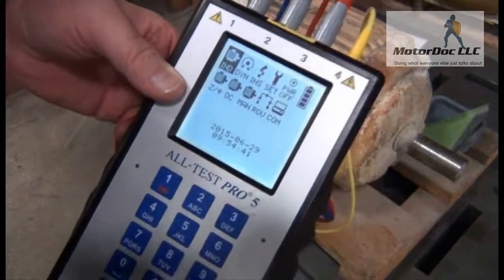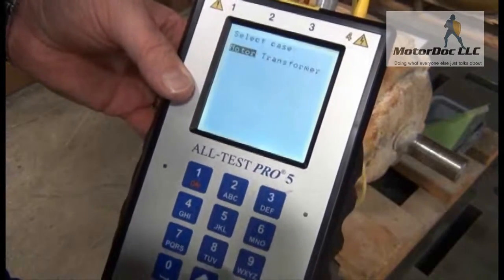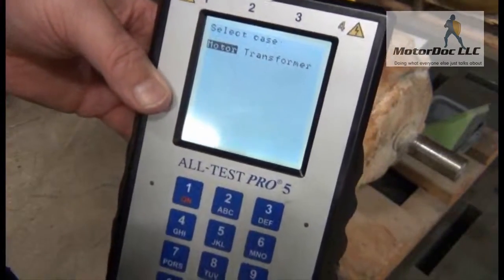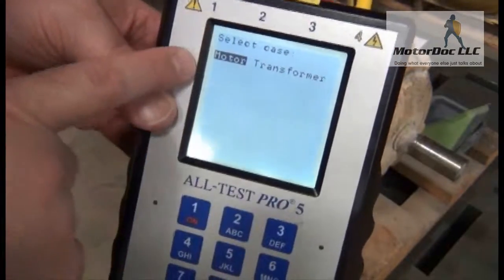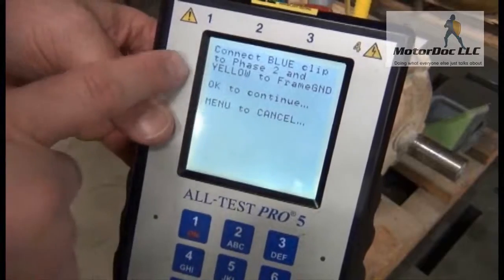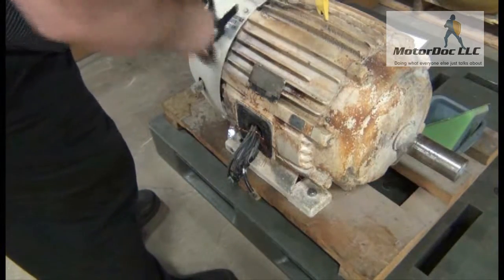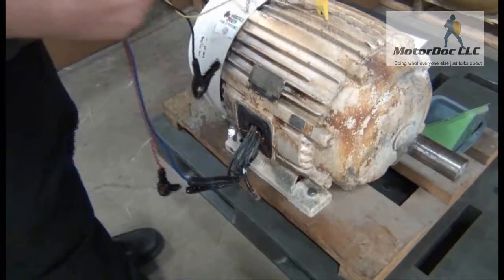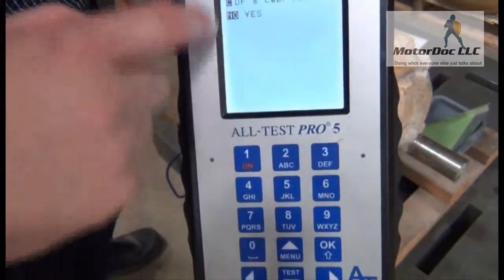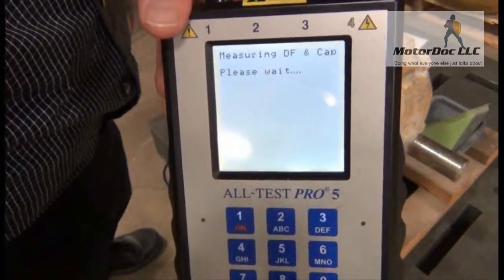Okay. Now we're going to do the demo on the other features, which in this case, I will be doing the motor test. So I select that. And I've got the option of doing a motor or transformer. Cause yes, this will do transformers, DC motors, coils, do comparisons, trending and everything else. So this case, I'm going to do the motor press. OK. Does the same thing as the other measurements, the yellow and the blue. So there I have my set up. Press OK. Dissipation factor and capacitance. Yes. Press OK. Allow it to run.